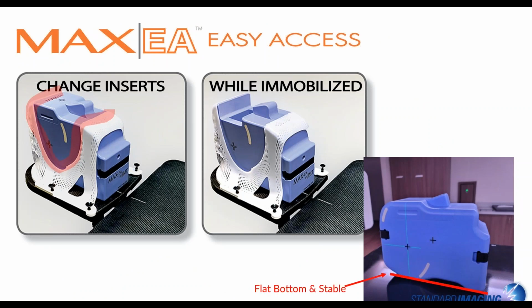So you see here, the Phantom is machined flat on the bottom, so you can use it without any cradle or any kind of head cushion. You simply slide it against an indexing bar for repeatable setup, and then with the mask system, you can apply an open thermoplastic mask, and then be able to remove the cover without disturbing the setup at all. And the mask can be formed around the cover.